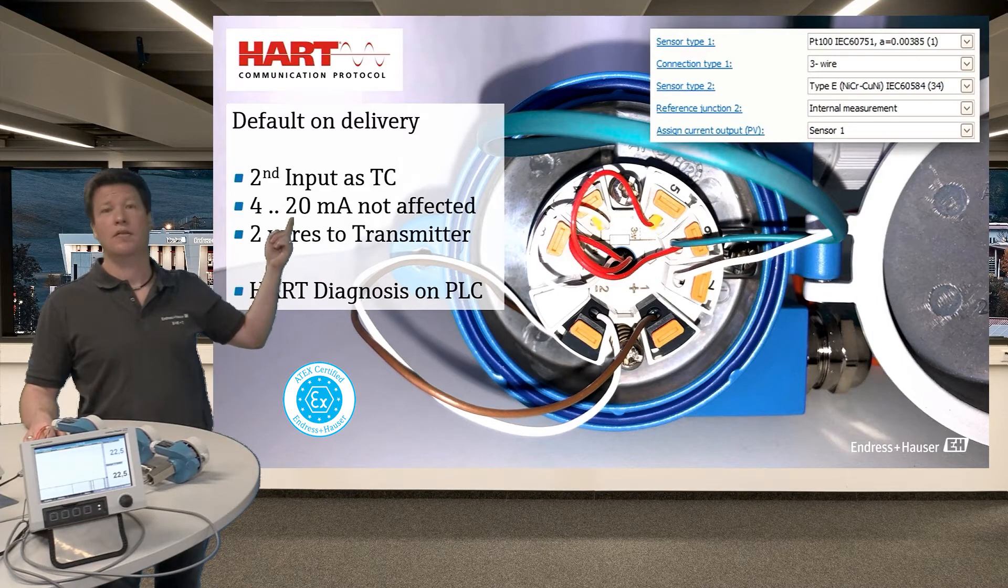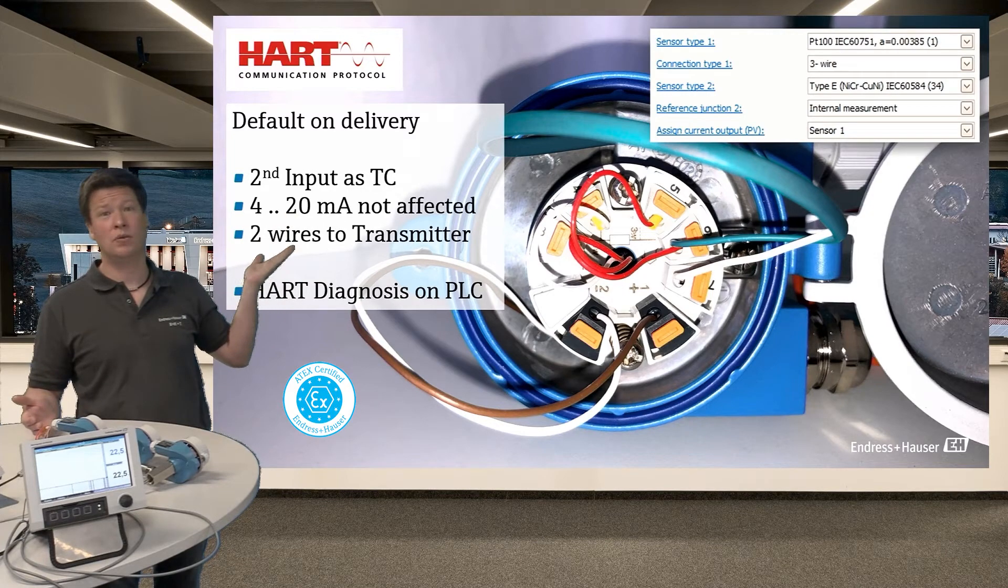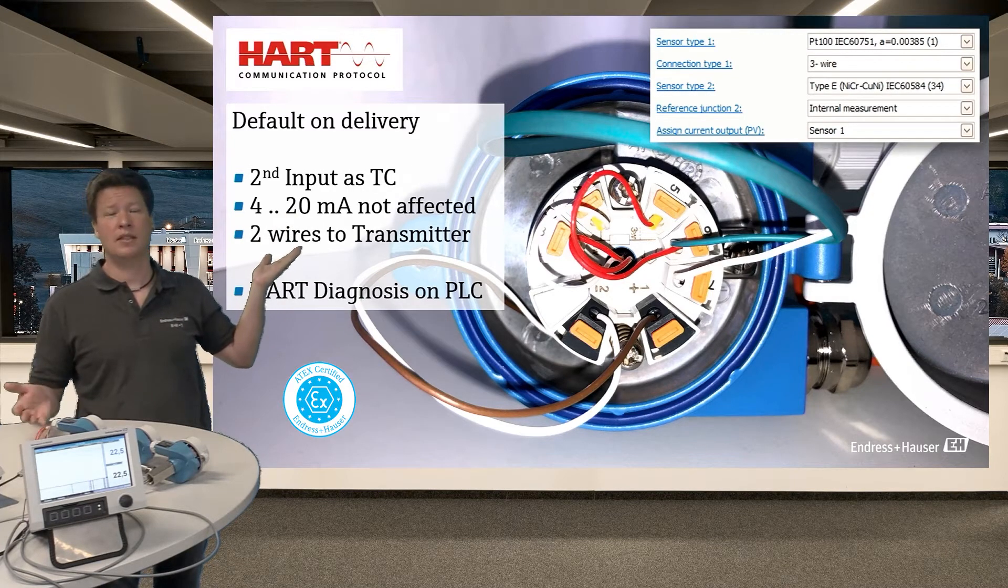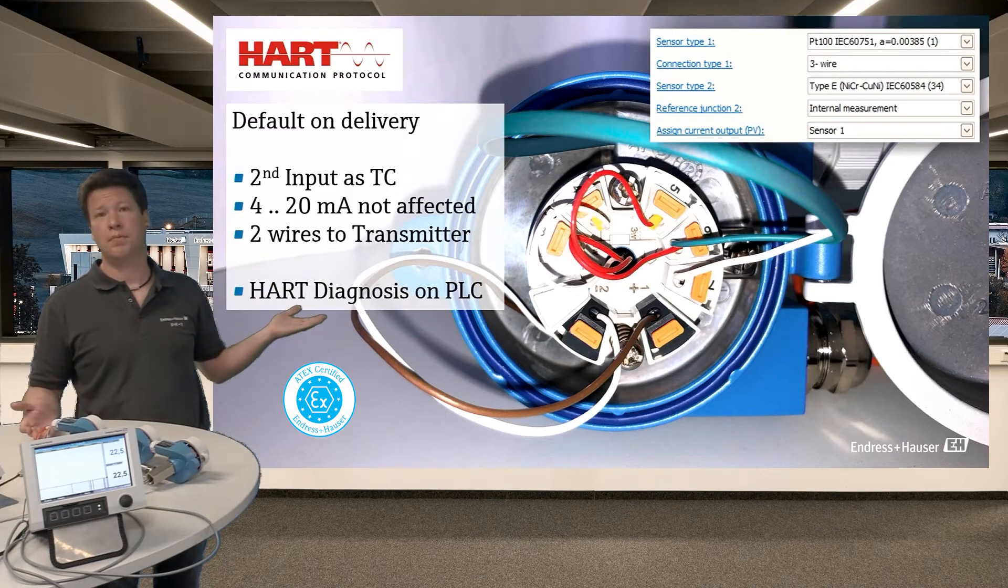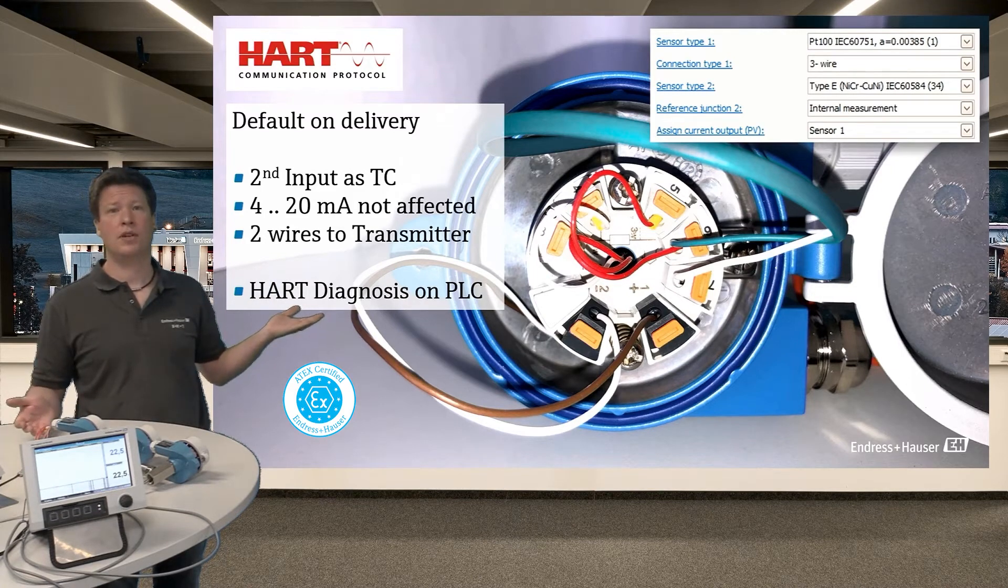Benefits are 4 to 20 milliamp signal is not affected. We need only two wires to the transmitter, standard installation. But the PLC must support HART diagnosis.